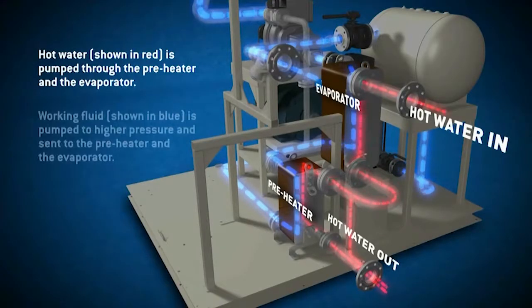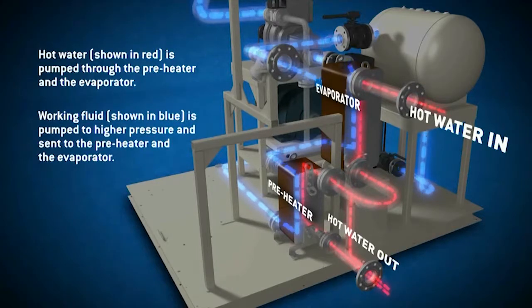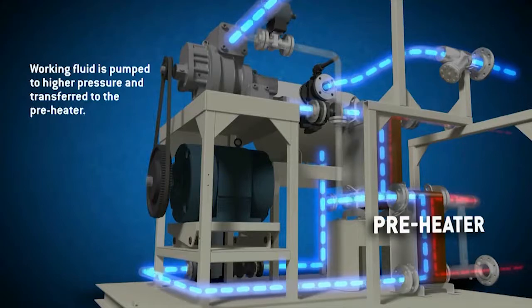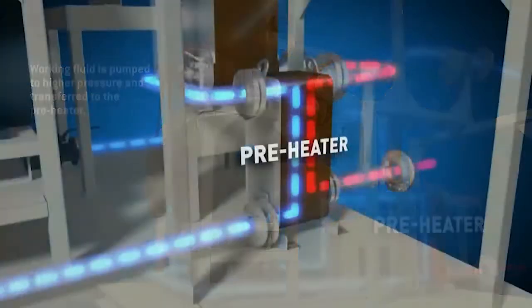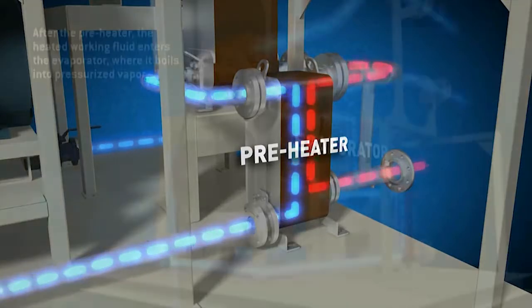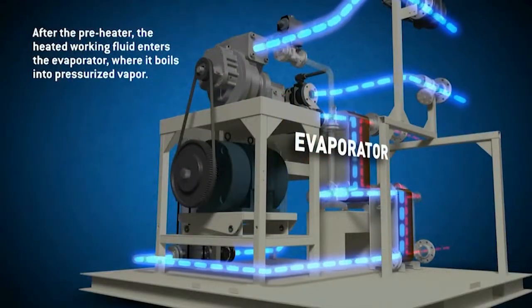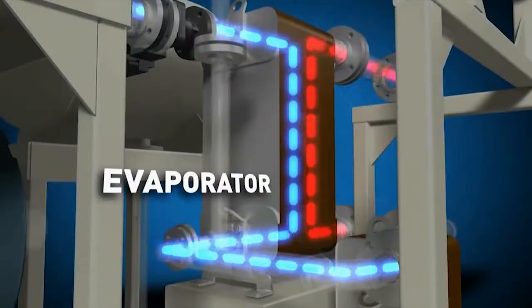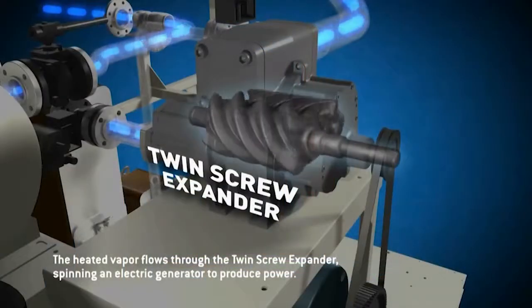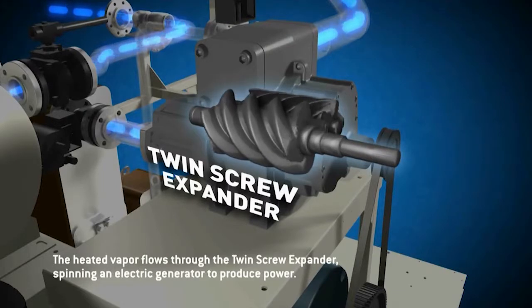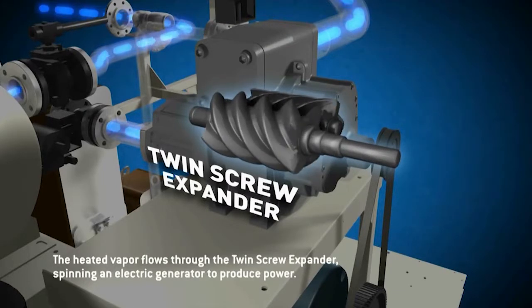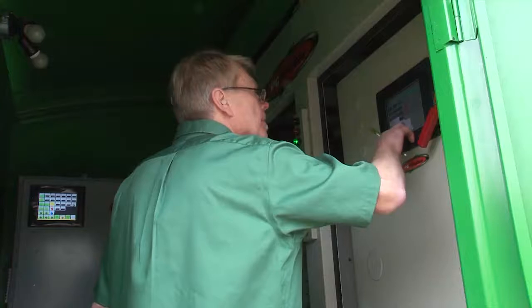Hot water, shown in red in this graphic, is pumped through the preheater and the evaporator. An environmentally friendly working fluid, shown in blue, is pumped to higher pressure and sent to the preheater and the evaporator. After the preheater, the heated working fluid enters the evaporator, where it boils into pressurized vapor. The heated vapor flows through the twin screw expander, spinning an electric generator to produce power.